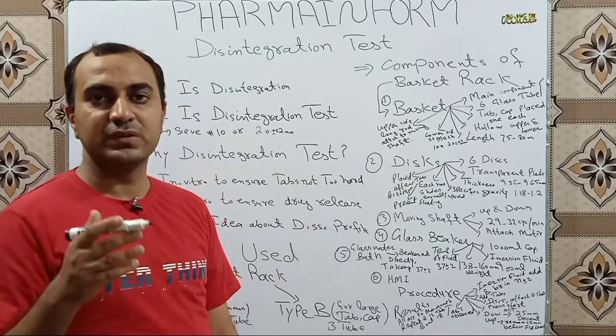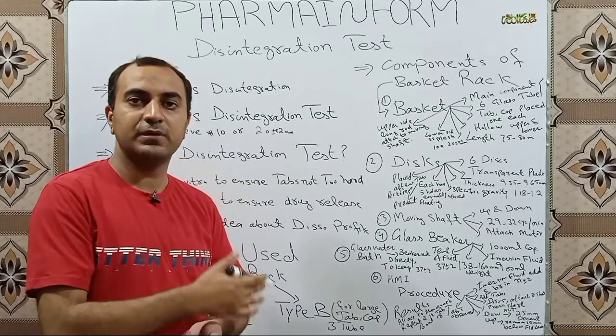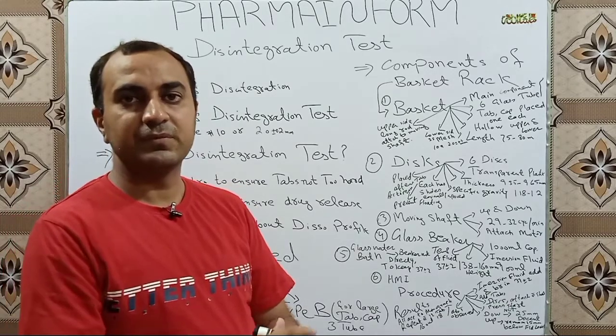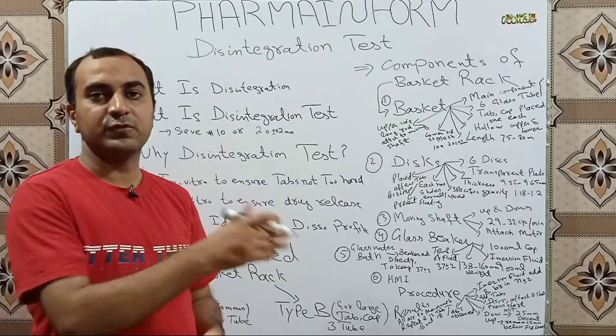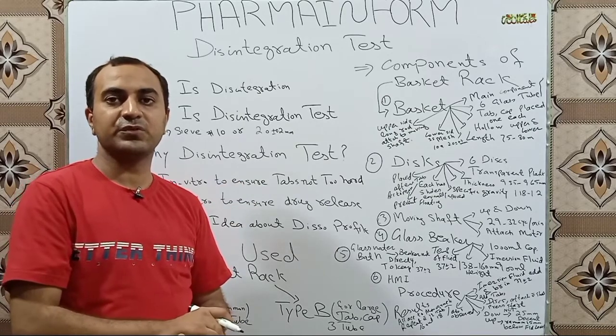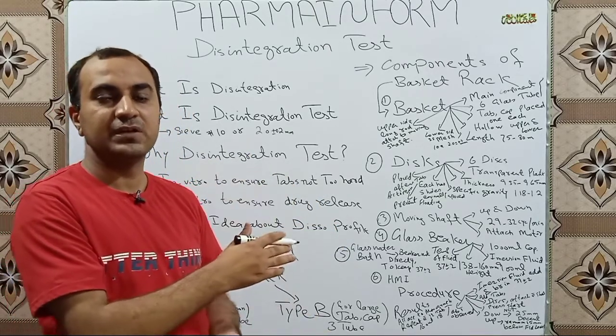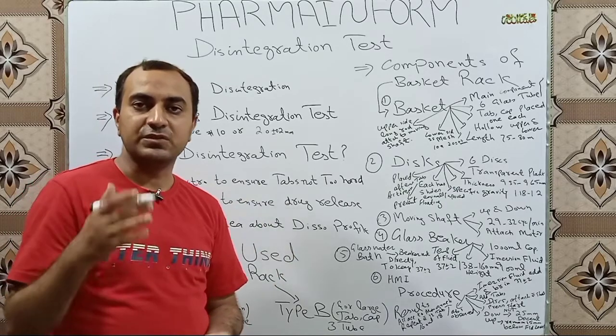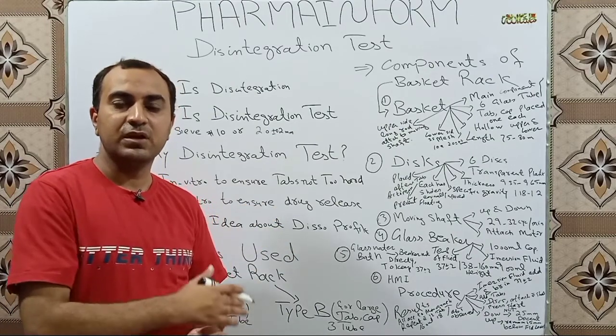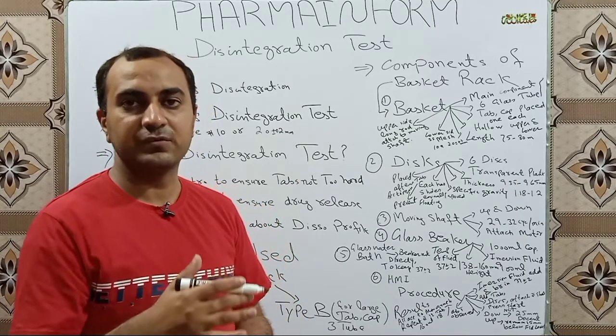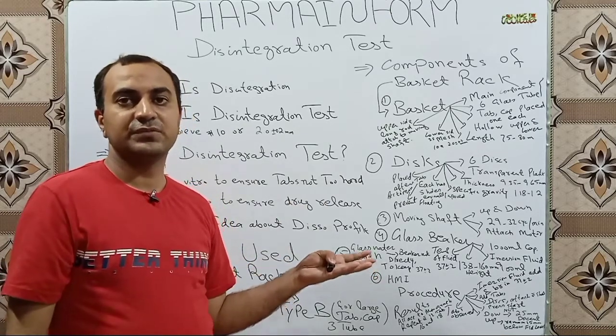What is the disintegration test? Simply, it is the test used to check how much time is required for a specific type of tablet or capsule — like core tablets, coated tablets, or effervescent tablets — to disintegrate. This time determination test is known as the disintegration test. In the disintegration test, tablets or capsules are placed in the apparatus; when they come in contact with fluid, they break down into small fragments that pass through sieve number 10 or 2 mm mesh leaving behind no hard mass.